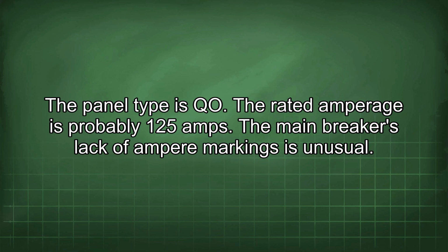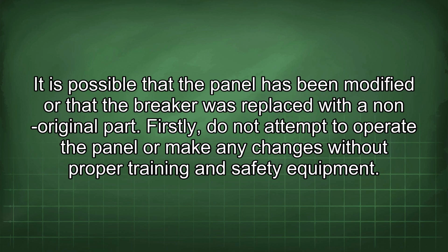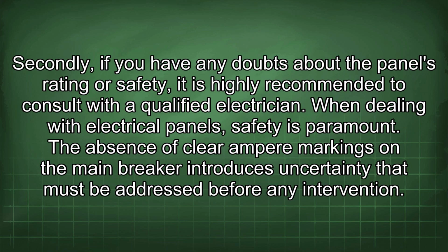The main breaker's lack of ampere markings is unusual. It is possible that the panel has been modified or that the breaker was replaced with a non-original part. Firstly, do not attempt to operate the panel or make any changes without proper training and safety equipment. Secondly, if you have any doubts about the panel's rating or safety, it is highly recommended to consult with a qualified electrician. When dealing with electrical panels, safety is paramount.